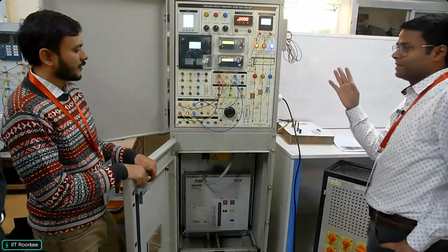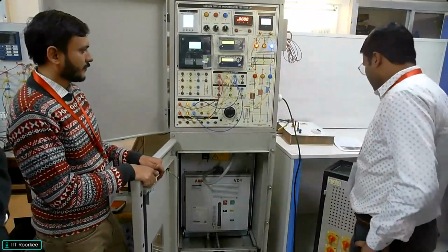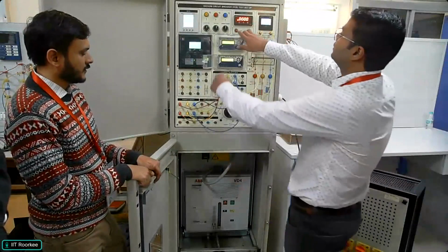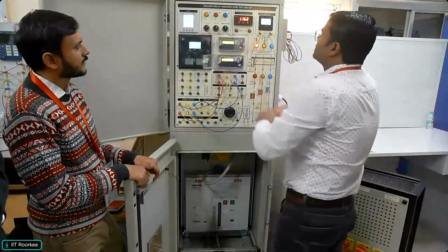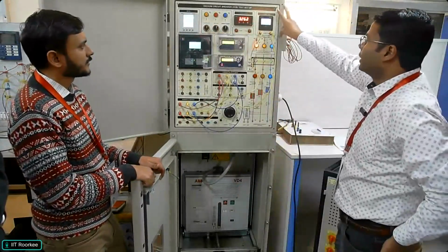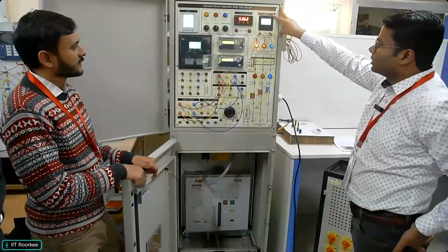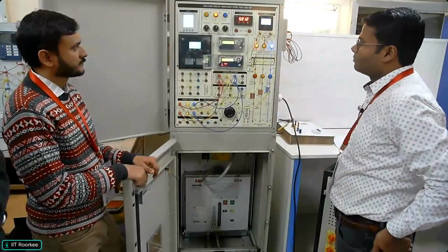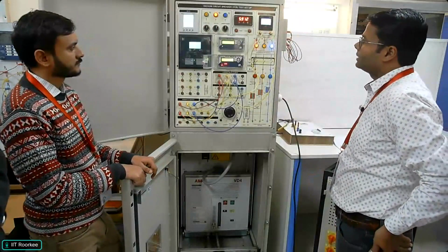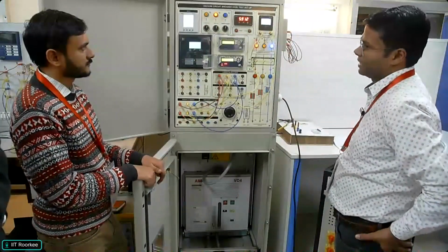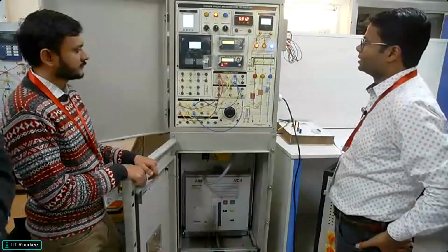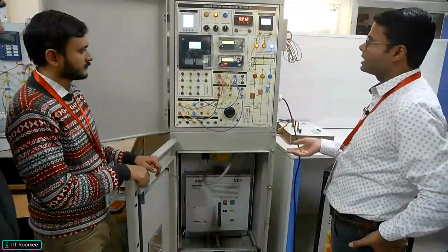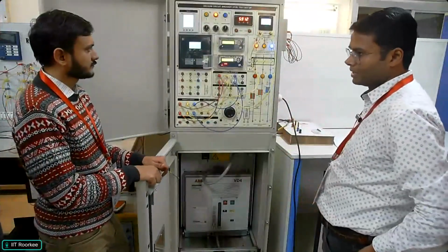It has taken 17.77 seconds for 1 ampere. When we go for the 2 ampere load, it will take less time compared to 1 ampere. Now we can see the value of current is 2.172 and it has taken 5.912 seconds. The total time is nearly 5 seconds, so further it will take less time. That's why we are not doing more than 2 ampere.